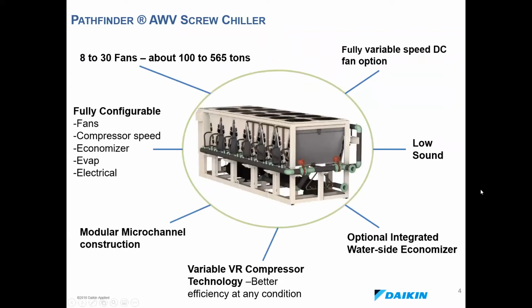Okay, so like I mentioned, there's a lot of items on the configurability of this product. So here's just a slide that's going to outline those. You got 8 to 30 fan options. That makes the range of 100 to 565 tons. We've got the fully configurable fans in terms of fan numbers, as well as the DC and AC options on the package right now. You can also change your compressor speeds, your RPS, rotations per second. You can also change your refrigerant economizers. There's an option for an integrated water side economizer. You can change your evaporators and your electrical as well to dial that in for your job.